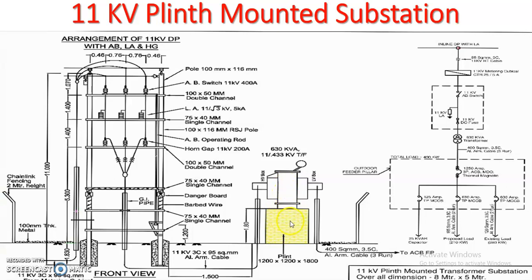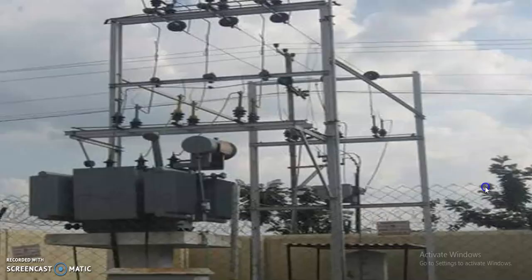This transformer is mounted on the plinth which is prepared with the help of cement concrete. So this is our 630 kVA transformer. Its input or HV voltage is 11 kV and secondary, that is LV voltage, is 430 or 440 volt. This is our plinth mounted substation. So we'll see in detail.